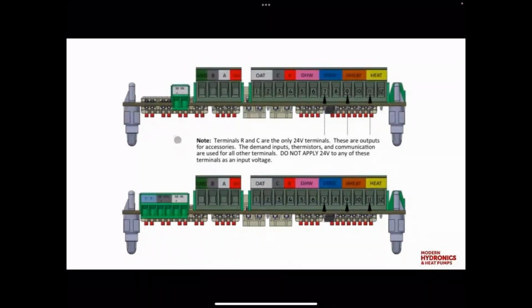And of course the electric backup has all the same settings available to where you can adjust how aggressive the electric backup is. Obviously, with the boiler, you can get a little more capacity out of it than 9 kW, depending on size of boiler and size of piping and all that sort of stuff. But I feel like this is a pretty big shift in the world of hydronic heat pumps and makes it so much nicer and easier to incorporate a dual fuel system, which I happen to be a big fan of. It opens up a lot of possibilities and a lot of flexibility when it comes to size of projects and type of zones, and hitting all the requirements that building owners or homeowners are looking for.